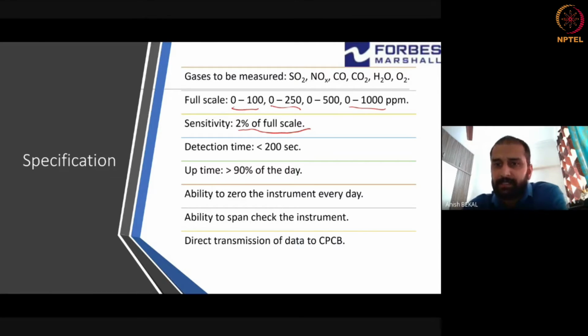And when they say sensitivity, this is beyond all interference, all fluctuations, everything. So you put in interference, fluctuations, changes because of temperature or anything of that sort, they all have to come within 2% of the full scale. Detection time, 200 seconds, they typically allow, but for some applications we want as low as 1 second. They also require that your sensors should be available 90% of the time in the day. That is also very important, because every day you would require a calibration of the instrument, and you would spend the rest of the 10% of the day possibly trying to calibrate.